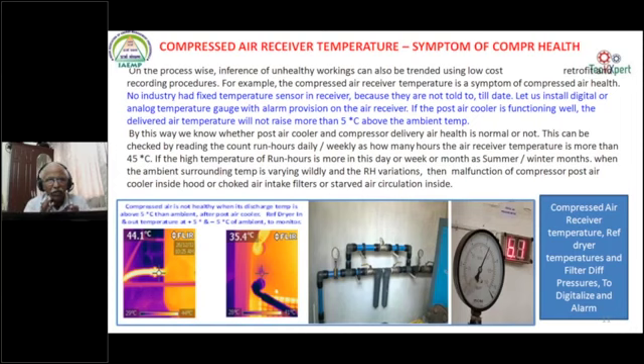One more reason is the ambient air. The heat transfer across the ambient air, every utility or every machine wants to make use of it. So if you want heat transfer across the ambient, definitely you try to make your system big enough, with more volume, and separate. We have to have discrete subsystems as far as possible. And if the dryer or the compressor post-air cooler is not effective, automatically the temperature goes to 45 degrees and the compressor FAD will come down.